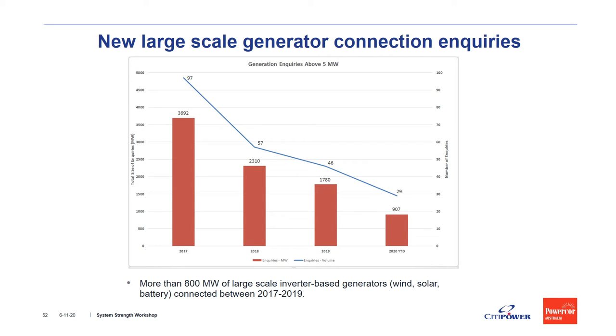In the last 5 years, we have received a significant number of new inquiries to connect large-scale generator to our network. And most of them are for inverter-based generators, such as wind, solar, and battery. We have managed to connect more than 800 megawatts of new generator between 2017 and 2019. As you can see in the graph, the number of new inquiry and the volume of new inquiry have been trending down, and it is due to several reasons. One of them is the increasing level of complexity and the time taken to assess a new generator connection, especially considering the impact of those new connections on system strength.